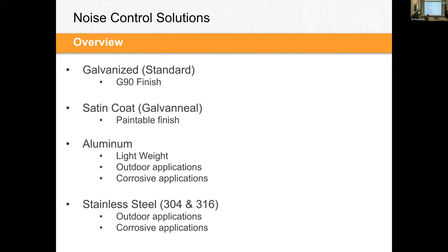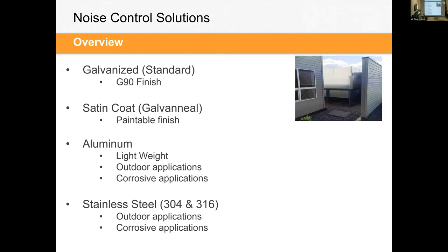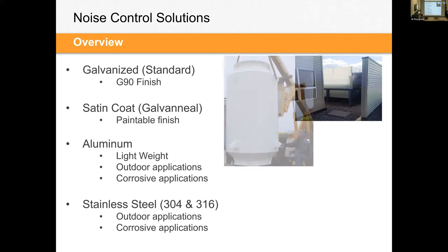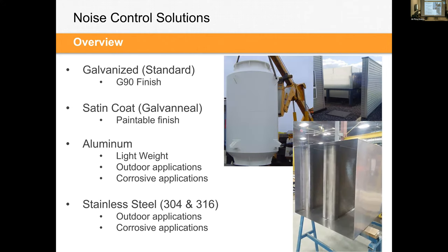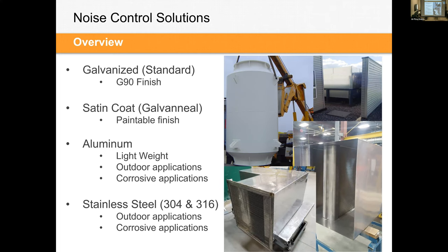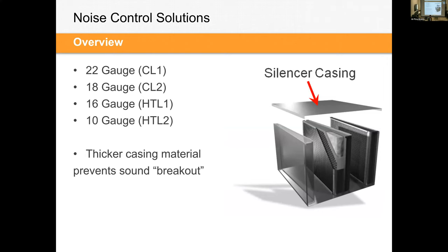From a material and construction standpoint, silencers use whatever material is necessary to match the connecting ductwork. In general, when you're selecting or designing a system, if the system is made out of aluminum for corrosion or weight, the silencer would also be designed and built out of that same material. Stainless steel is common for corrosive environments, laboratories and fume hoods, where you're worried about corrosion or contaminants getting into the duct system. The material can really be varied depending on your needs and your construction.